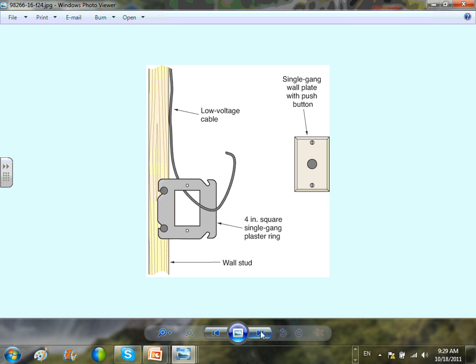Do you guys know in low voltage, do I need a box for low voltage? Unlike high voltage, you need a box. Can I terminate a 120 up in the air here, just have a splice like some people do? No. If you terminate high voltage, you need a box. If you terminate low voltage, you don't need a box. Take this coaxial cable. If I have a coaxial cable, you see them without a box like this. It's a good idea to have a box, but you don't need a box for low voltage cable.